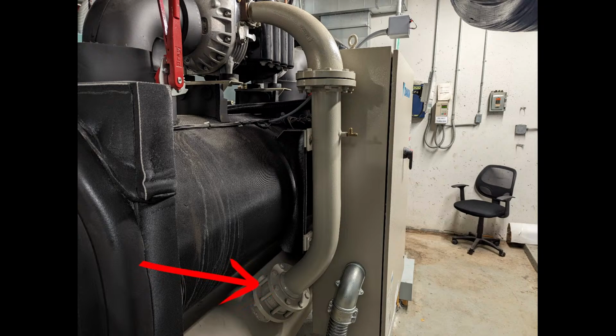So what that does is, I don't have a good depiction of it at the moment, it actually has a line that connects to the discharge up here and then runs over to the condenser. And what it's doing is it's a metering valve that opens up and allows some gas to bypass the check valve. And what that does, it doesn't eliminate the check valve from hammering or chattering, but it does reduce it significantly. So it takes a lot of that mechanical stress that was put on the check valve out of it, and allows some of that gas to flow around without it being too much, right?